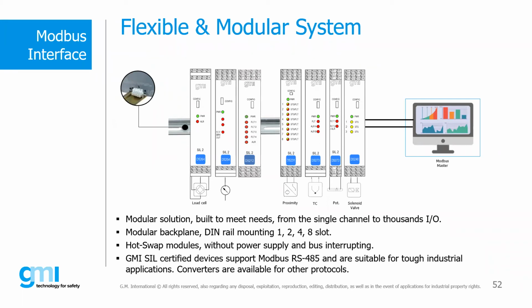There are two versions of the protocol on serial port RS485 by default, but also RS232 and on Ethernet. Each peripheral that needs to communicate via Modbus is assigned a unique address. Each of these can send a Modbus command, although generally only one peripheral acts as a master. A Modbus command contains the Modbus address of the peripheral with which you want to communicate. And again, only the latter will act on the command, although the other devices also receive it.